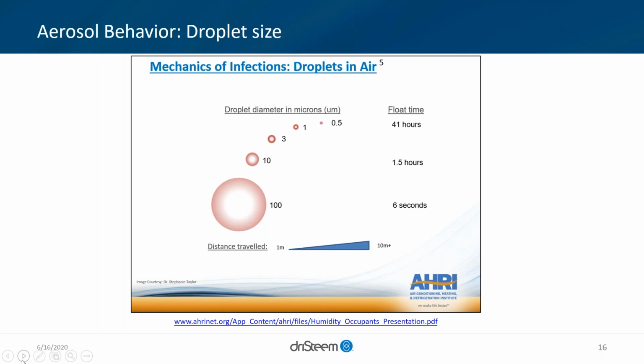As lower ambient RH desiccates the aerosol, it may remain airborne for an extended period of time. Some studies have shown as much as 72 hours. From the perspective of built environment, we have to consider the capacity of our filtration systems to capture small particle size. We should recall with SARS that it was possible for aerosol viral particles to float not only along corridors, but also out of buildings and be pulled into the ventilation systems of adjacent buildings as much as 600 feet away.